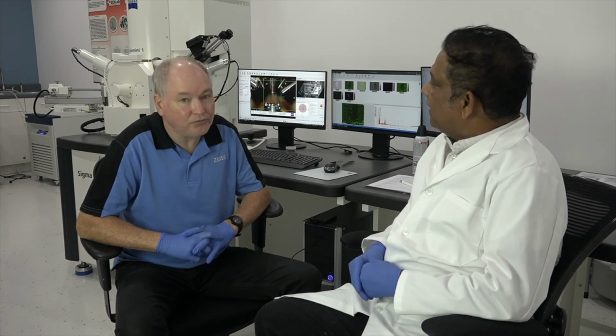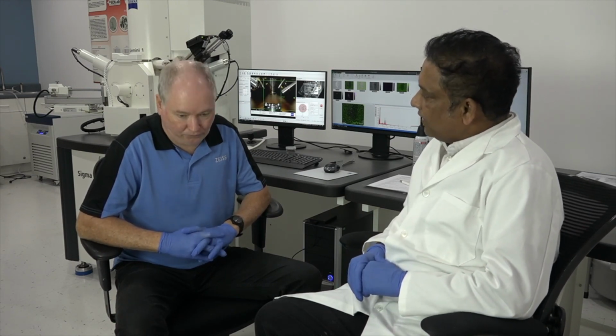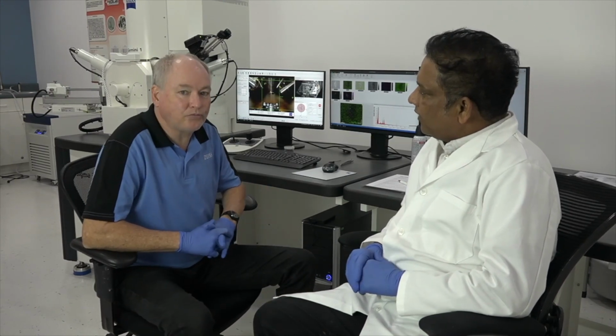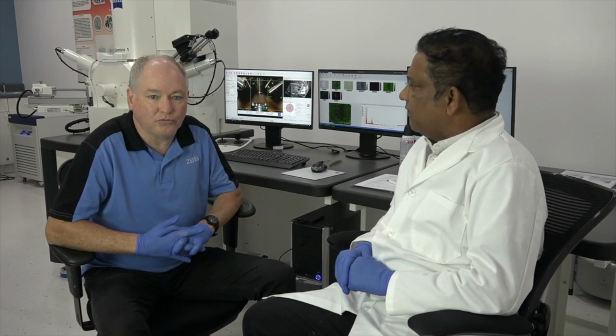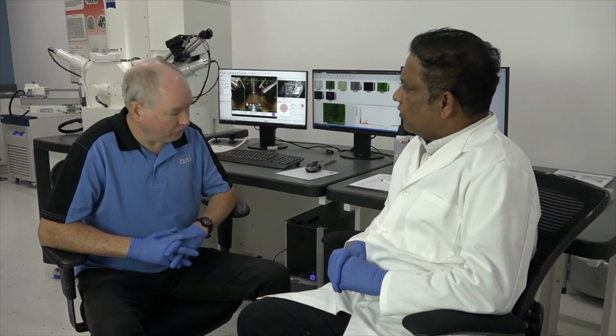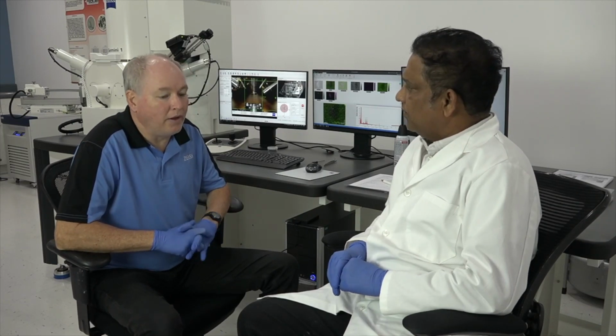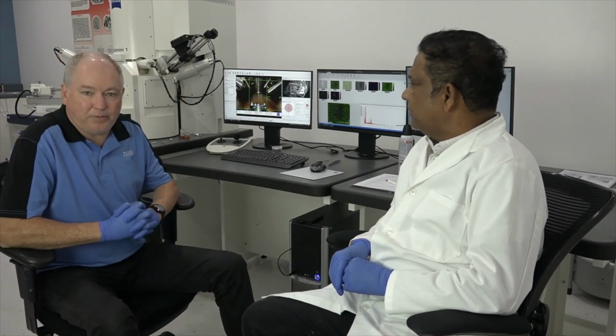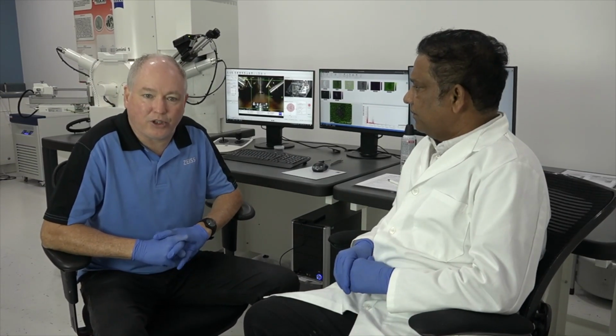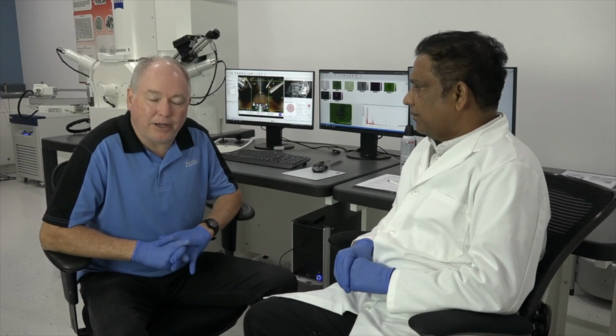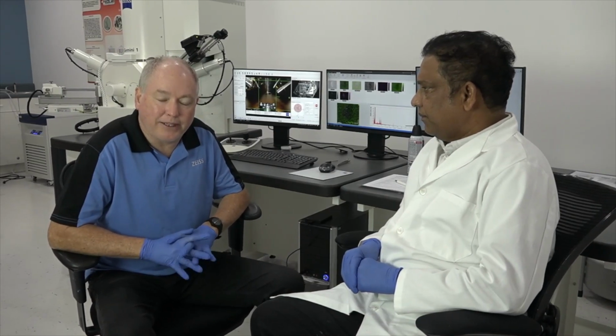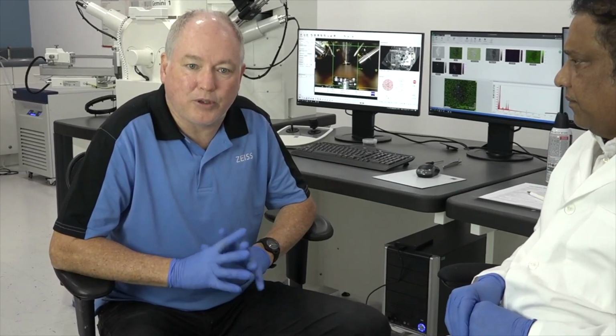Very good. So I think this is one of the very top of the line models of the Zeiss microscope. So what do you overall recommend to maintain so that we can optimize the function and keep working with this microscope as we intended to? Very good question. Yes, this is the Sigma 300 series field emitter microscope, a very high powered microscope used for high resolution work. To maintain the quality of the imaging, we recommend using nitrogen to backfill the system when we vent it. Also, as you can see, wearing gloves to handle the samples keeps everything as clean as possible, and maintain the temperature and humidity in the room.